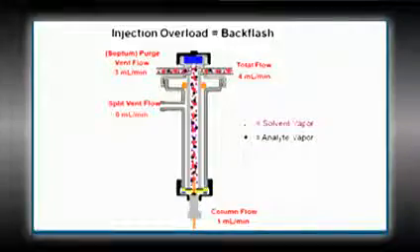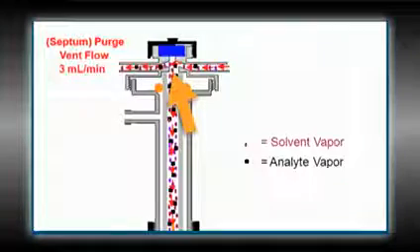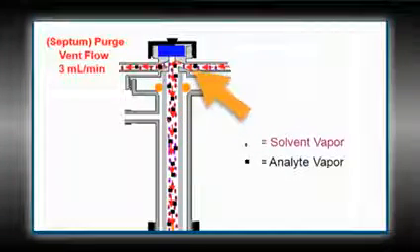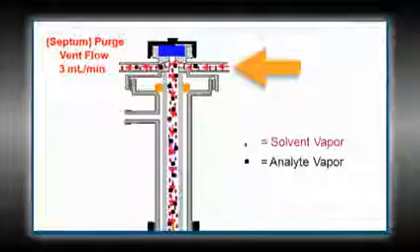Let's discuss exactly what backflash is. This happens when the vapor volume exceeds the liner volume. And where does the sample go? Everywhere. The problem is that the vapor can condense on the cooler part in the top of the injector lines, or wherever, because it isn't as hot there. That condensed sample will still have a headspace or a vapor which can be swept forward onto the column.